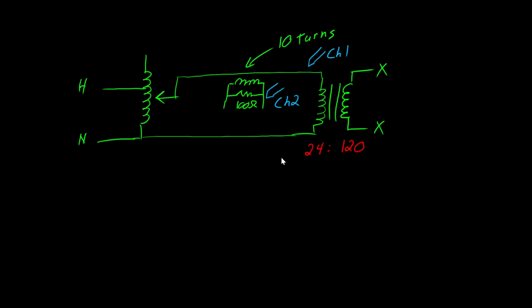This is necessary because we are going to apply an excess voltage to the winding. As it's currently configured, we could potentially apply 120 volts to the 24 volt winding. As you'll see in a moment, that's not possible because it will destroy the transformer. However, we can apply lower voltages and incrementally increase the voltage to see what happens.